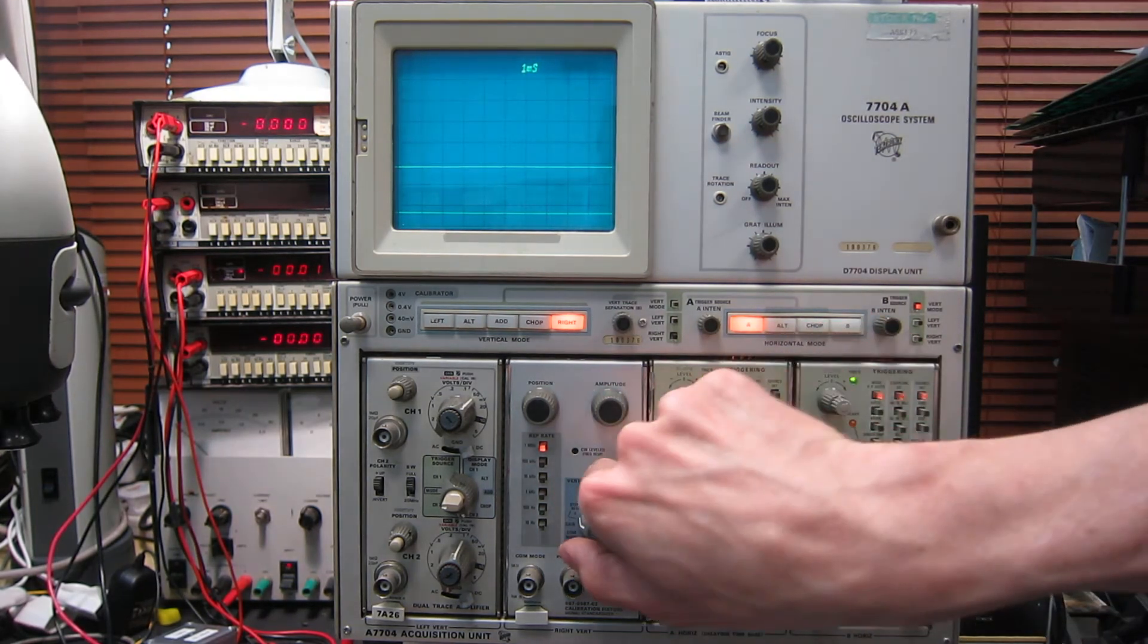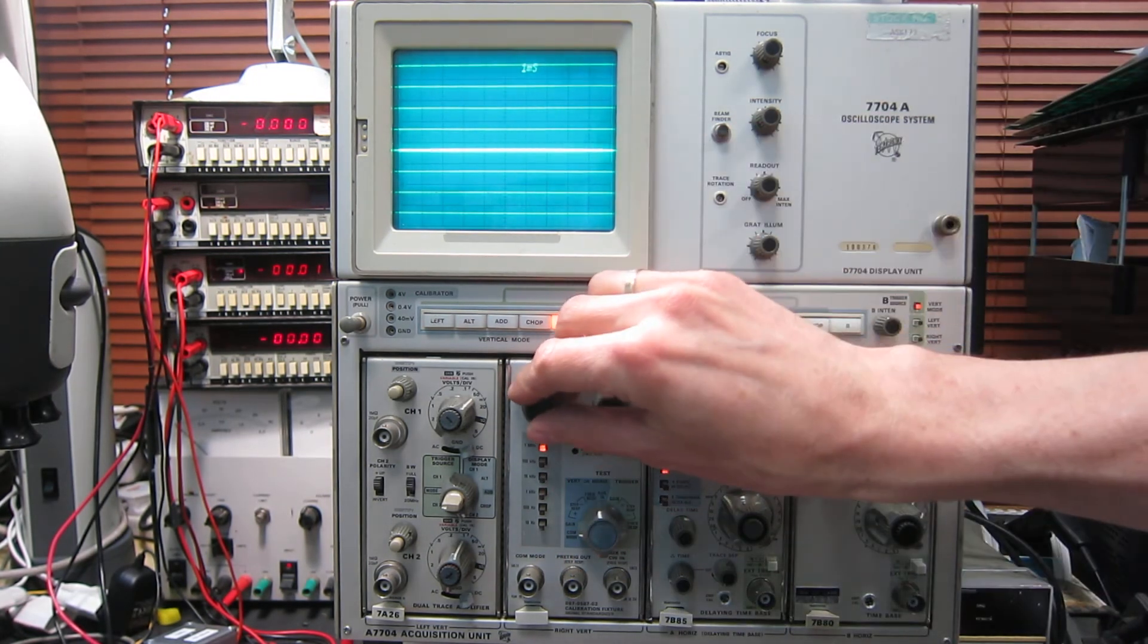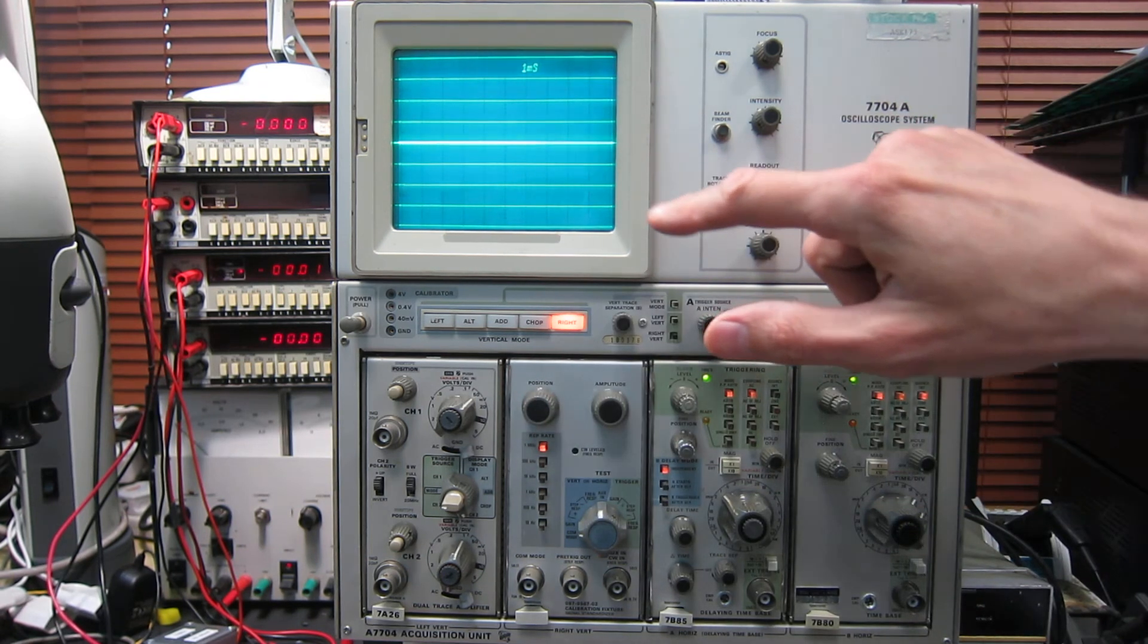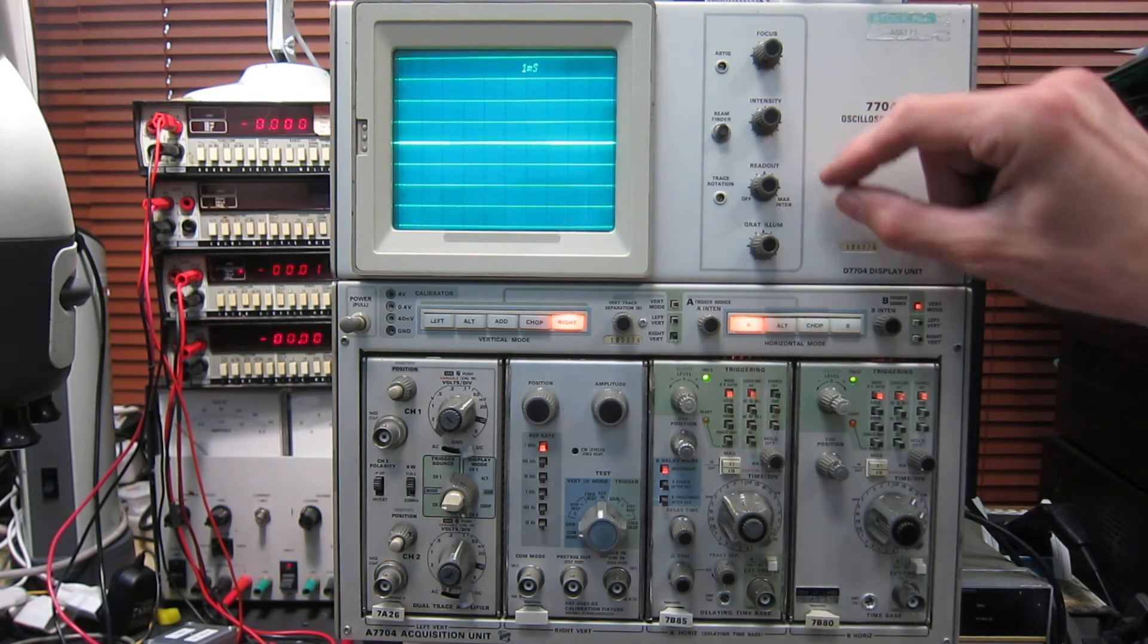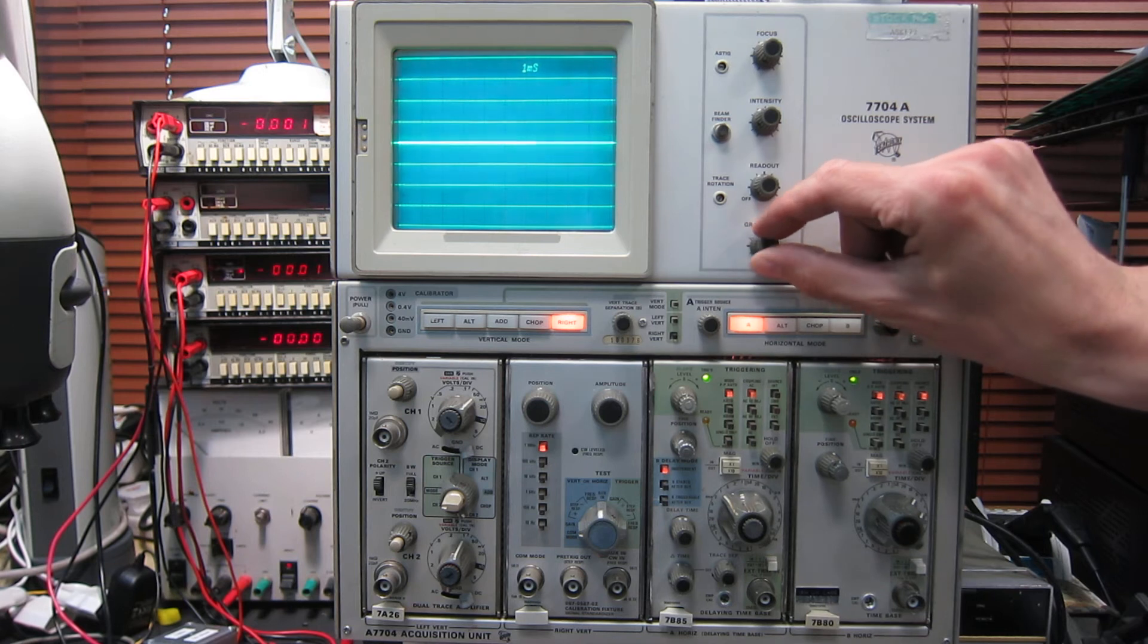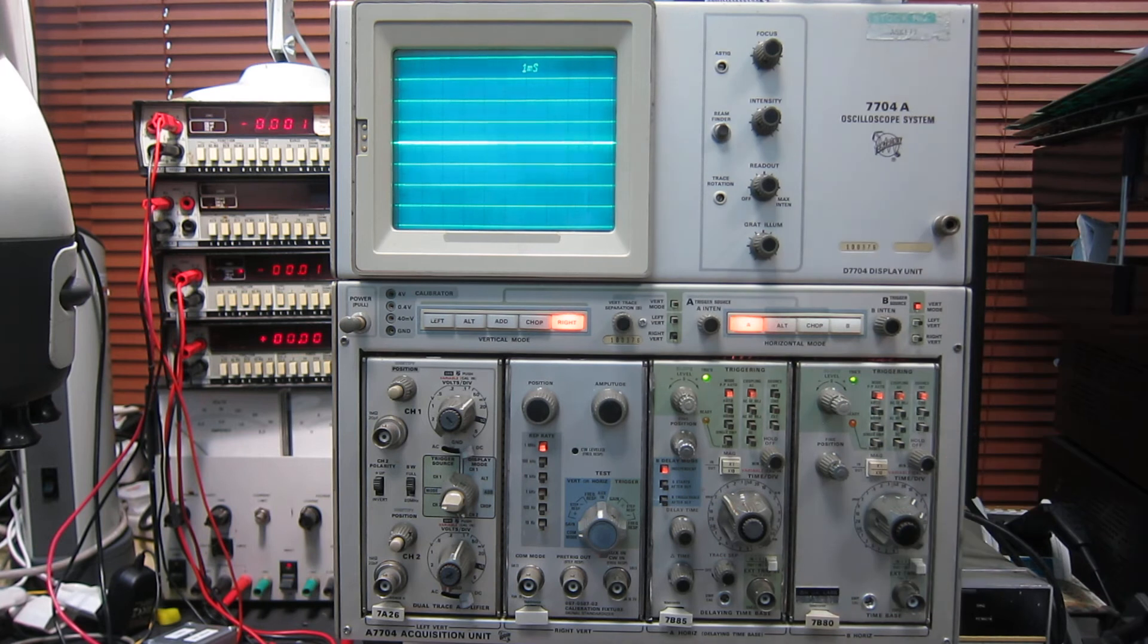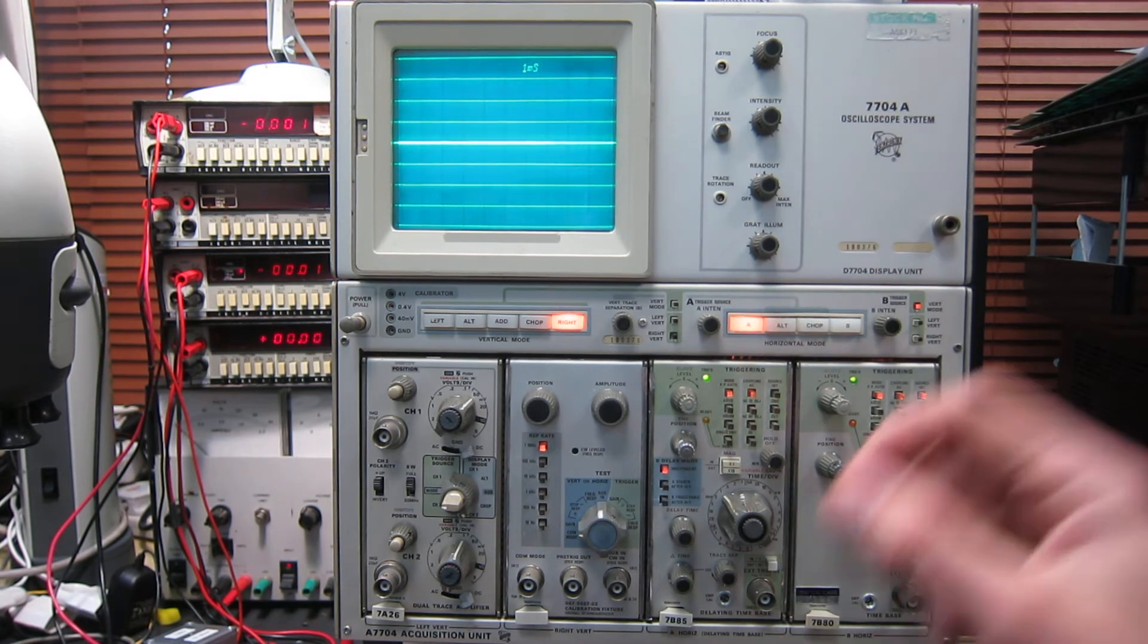So if I put it on the gain setting, turn the intensity up a bit, you can see this creates a grid of lines on the screen, which should line up with the lines on the Graticule. It may be a bit hard to make out. But you have to take my word for it, those line up perfectly with the Graticule, so the mainframe gain is adjusted correctly. So interchangeability of plug-ins should be no problem.